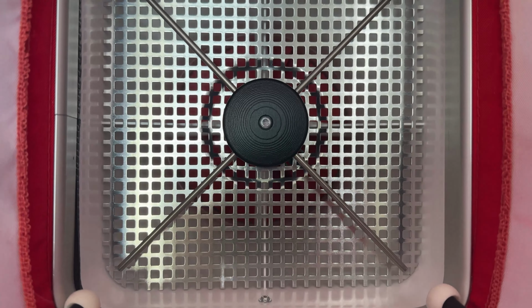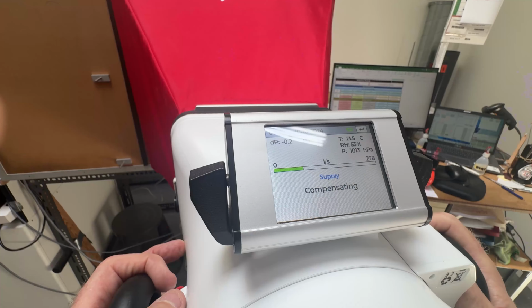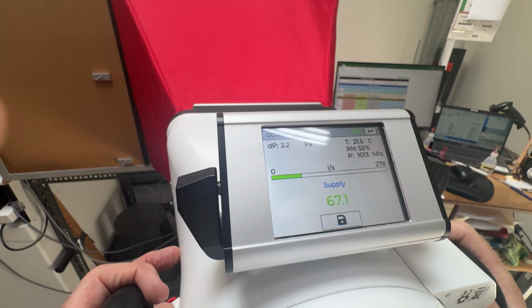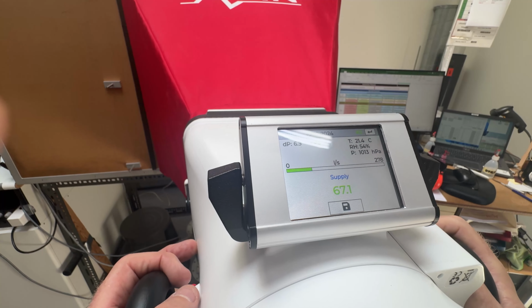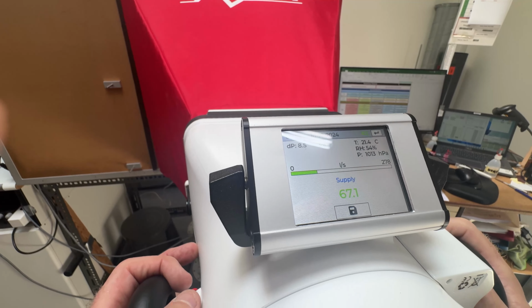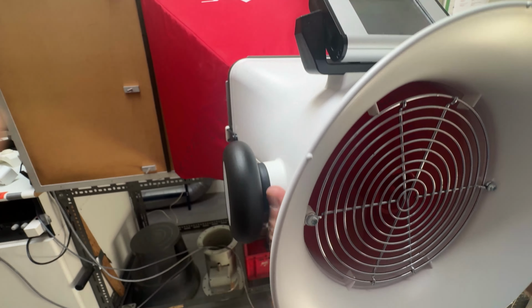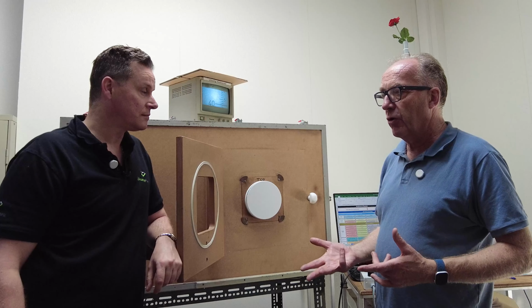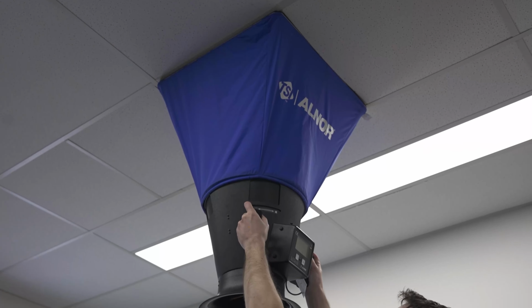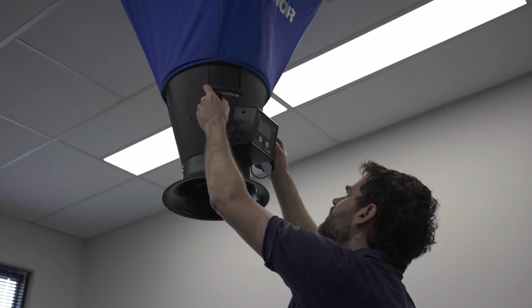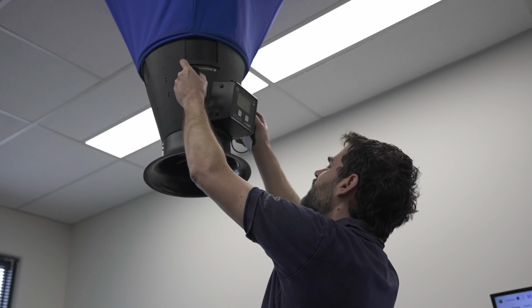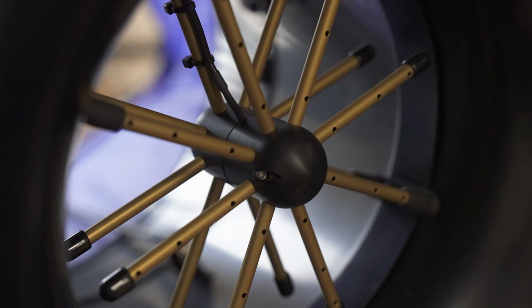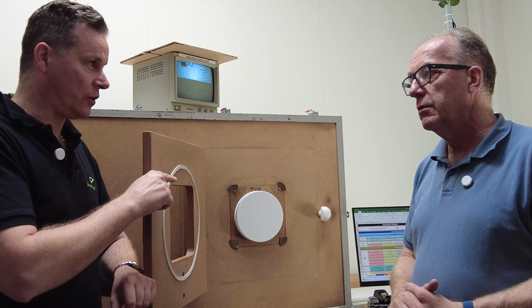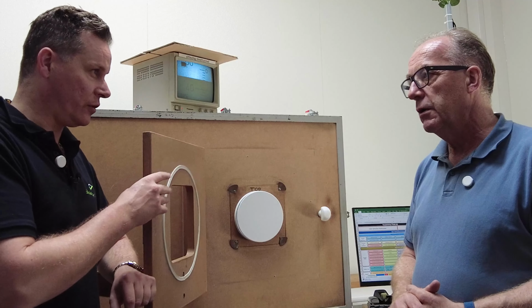When it is at 0 Pascal, the rotation speed of the fan gives you the flow. That is because it is calibrated on this rig. We make a table in the Flowfinder with rotation per minute at 0 Pascal resistance over the Flowfinder. And if you have a passive flow hood, you can't do that. You have all sorts of resistances. So your rotation per minute may be the flow, but it's only the flow with that passive flow hood on it. Yeah. So it's more important to have this pressure neutralization for the higher flows.